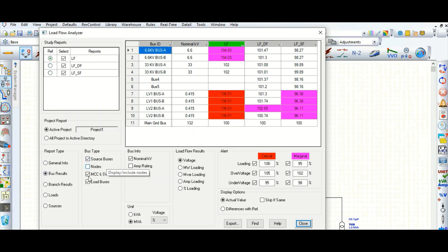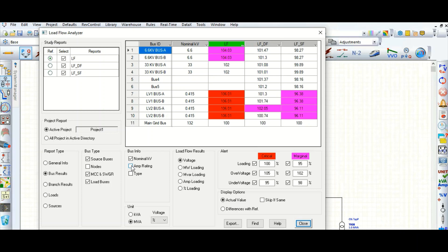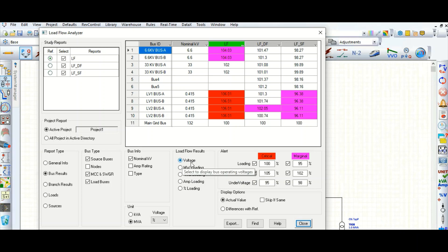You can filter by source bus, node MCC, switchgear, or load bus — check or uncheck as needed. Under bus info, you can view nominal kV and ampere rating. Since ampere ratings are not provided in our model, that column is not showing. Now here are the load flow results you can get from bus results: voltage, megawatt loading, ampere loading, and bus loading.